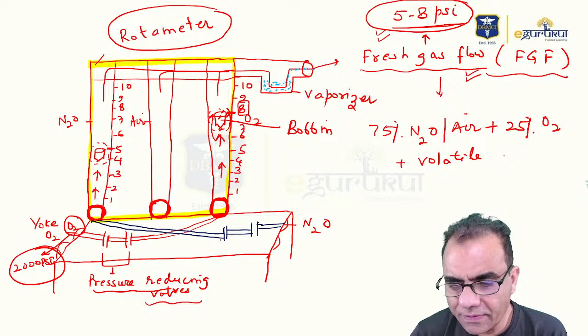And this final mixture, that is fresh gas flow, usually consists of 75% nitrous oxide or air, whatever you want to use, plus 25% oxygen, plus one of the volatile agents. So this is a very, very important fact that you must know: whatever may be the condition, oxygen concentration should never be allowed to fall below 25%. They have asked this n number of times in your exams also: what should be the minimum concentration of oxygen, what should be the optimal concentration of the anesthesia gas mixture. It must not be less than 25%, because if it becomes less than 25%, the patient can develop hypoxia.